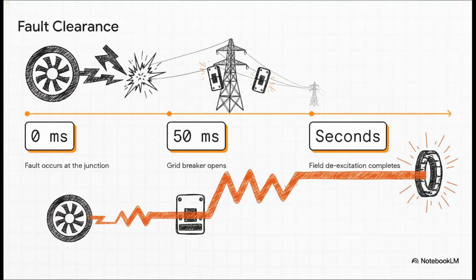Let's actually look at the timeline here to see how this builds. Bam! A fault occurs at T0 milliseconds. The relay detects it, and the grid breaker opens super fast. Let's say at T plus 50 milliseconds. Now, from the grid's perspective, the fault is totally isolated. But the generator's fault current contribution can persist for multiple seconds after the grid disconnects. Because the generator has its own independent excitation system, the fault current shifts as the generator's reactance moves from subtransient to synchronous, but it doesn't just stop. So you've got tens of milliseconds for grid clearance versus multiple seconds of continued generator feed if the excitation isn't actively removed. That is a staggering difference in the total amount of fault energy delivered to the core.